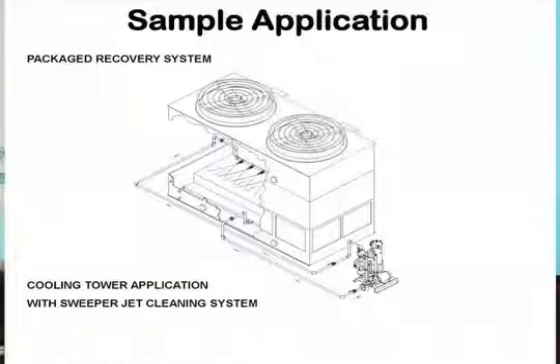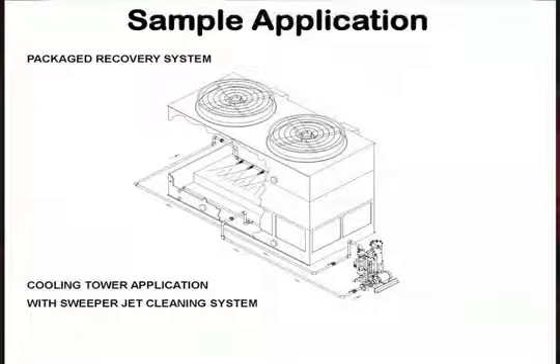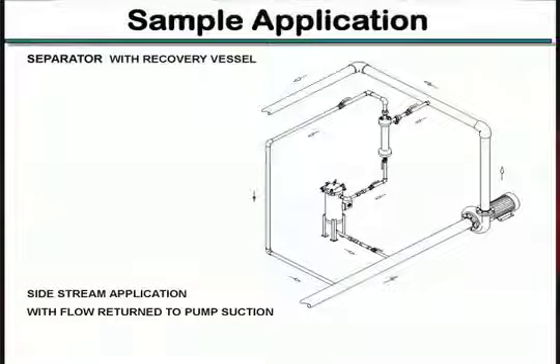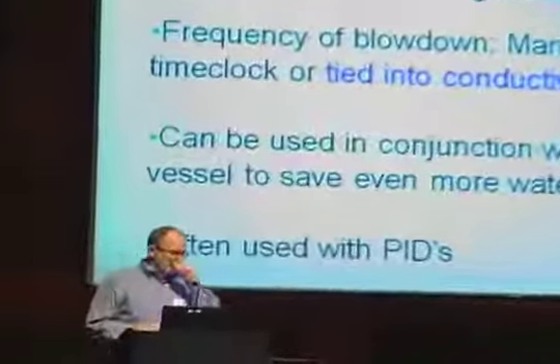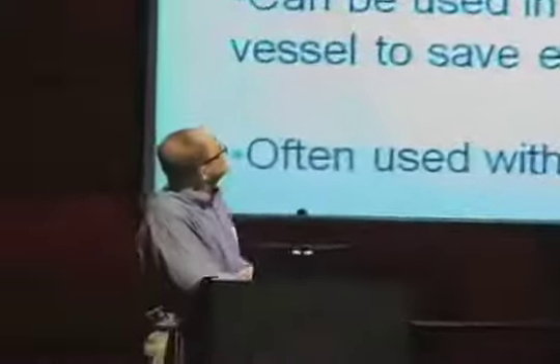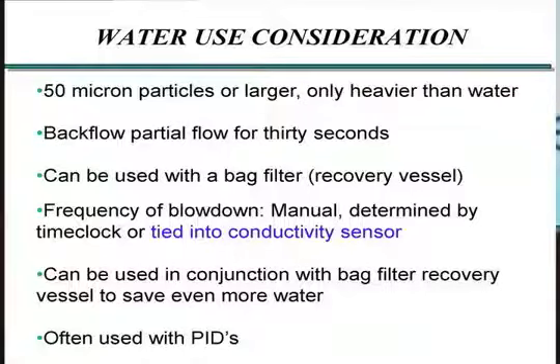These are often used and packaged with a pump. They can also be provided in a side stream or using the pressure drop across the main pump of the system to drive them. The main disadvantage of this type of system is it typically only affects larger particles and only heavier than water particles. And a lot of times you'll see concerns with cottonwood fluff in the system, and so this system is not really effective against that sort of thing.